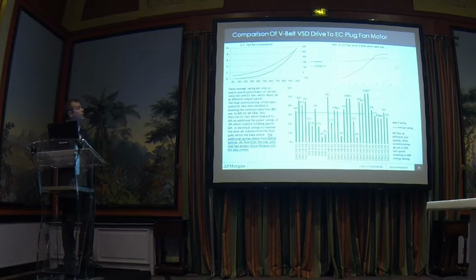So when you start looking at the EC fans up here, the lower you run them, the better. So cube law with fans, with moving air and pumping water: if you slow something down by 10%, you save 25%. So we're running at 60% there, so we're running about 2 kilowatts per machine. I couldn't find the other bit of data I had for the original running, but we were running at nearly 4 kilowatts to move the same amount of air out of that same machine.